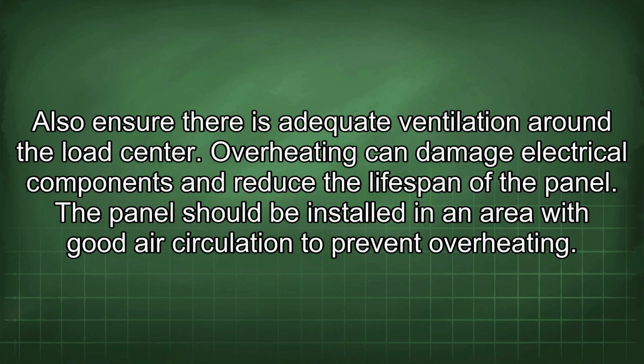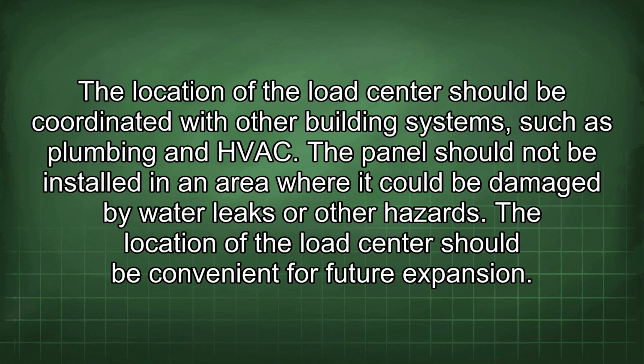Also ensure there is adequate ventilation around the load center. Overheating can damage electrical components and reduce the lifespan of the panel. The panel should be installed in an area with good air circulation to prevent overheating. The location of the load center should be coordinated with other building systems such as plumbing and HVAC. The panel should not be installed in an area where it could be damaged by water leaks or other hazards.